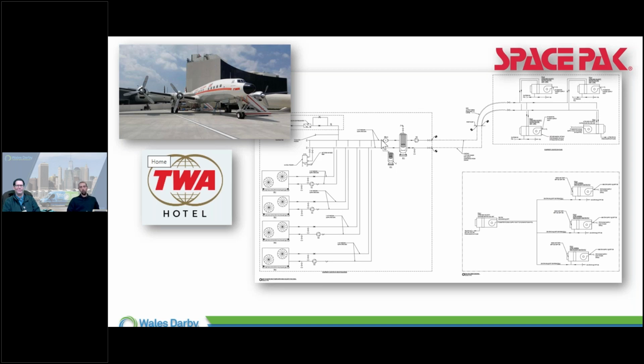We have some ways of doing that just with temperatures within the units, basically offsetting temperatures in the heat pumps. We could do a full setup, but I like simplicity. I know the guy that's got to go back there, I want to make his job easy. Sometimes designing a control strategy with staging may require a special skill set, and that's where I kind of go to the air-to-water side, because of how simple it is.